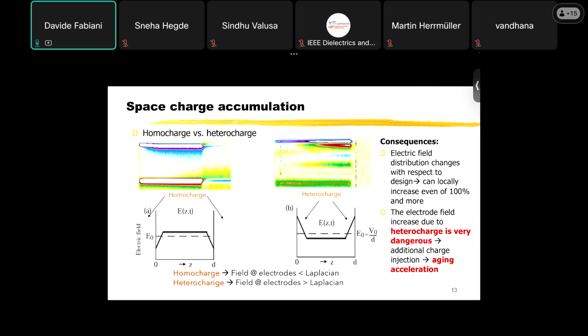Homocharge is shown here in a space charge pattern, with the thickness of the material on one axis and time of applied voltage on the other. We see negative charge accumulating close to the negative electrode, and positive charge accumulating close to the positive electrode — this is homocharge. It can reduce the electric field at the electrodes while increasing it slightly in the middle of the material. Remember, the integral of the field equals the applied voltage, so the applied voltage stays the same, but the local field can change due to space charge accumulation.